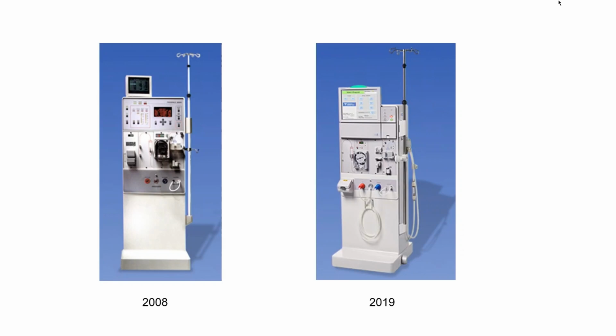Another company's IFU says, instead of prior to each treatment, verify conductivity with an independent means routinely. You know what routinely means in most places? When the biomed does their calibration, that's routinely, so the caregivers on the floor do not have to do it prior to each treatment. And all the manufacturers have followed suit. So hopefully you won't be cited by the surveyors for not doing conductivity prior to each treatment. Okay.